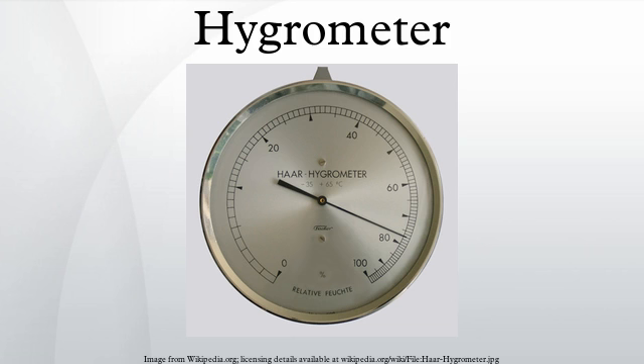An Australian study in the late 1990s found that liquid-in-glass wet bulb thermometers were warmer than theory predicted even when considerable precautions were taken. These could lead to RH value readings that are 2 to 5% points too high.